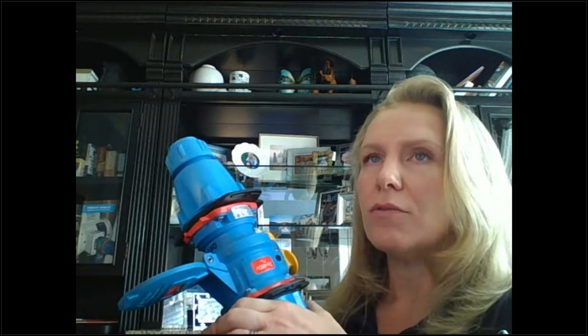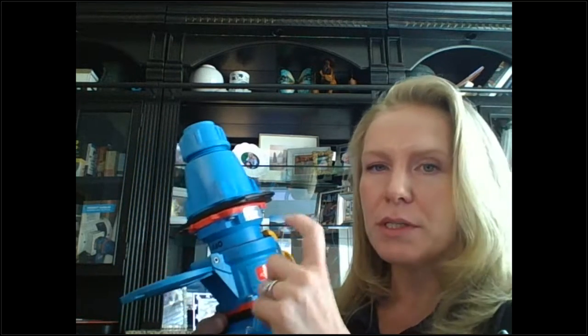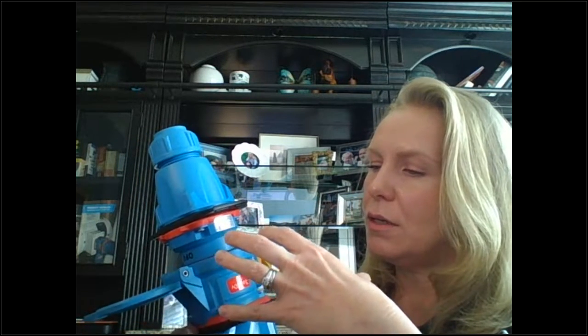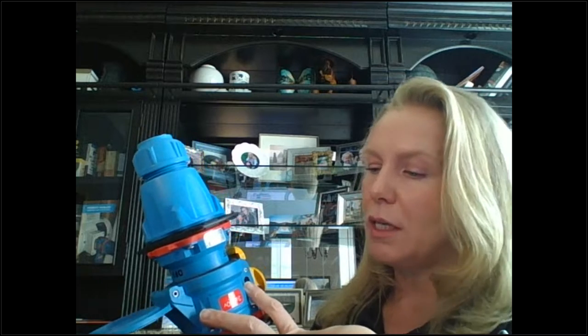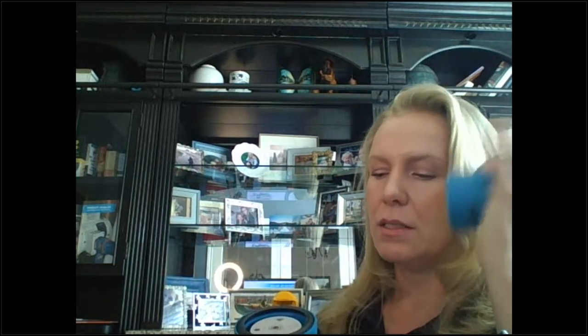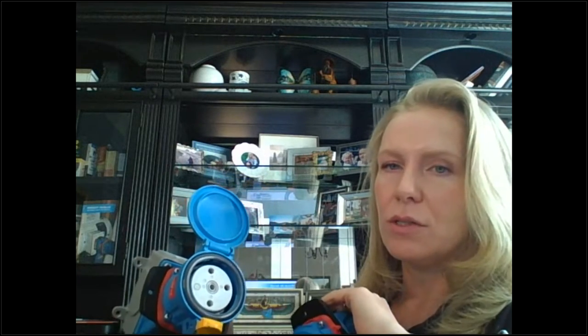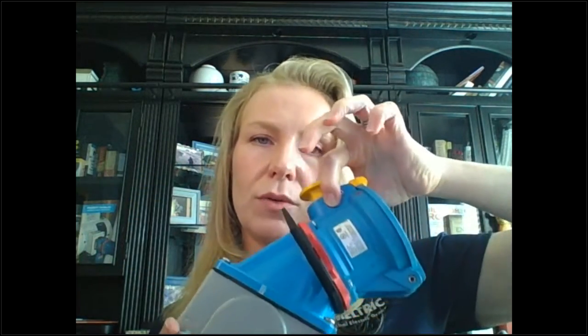When you disconnect a MELTRIC device, it disconnects in 15 milliseconds. There's an arc flash chamber inside so that the worker is never exposed to the potentiality of an arc flash hazard. And when you rotate the device to disconnect it, you've activated a dead front shutter, which isolates you from bare live conductors. So there's never a risk of shock. We've eliminated those two hazards from the workplace, the arc flash and the shock hazard. We can lock out, tag out very easily here on the plug, or you can get an extra lockout hole on the receptacle. So I'll start sharing again.